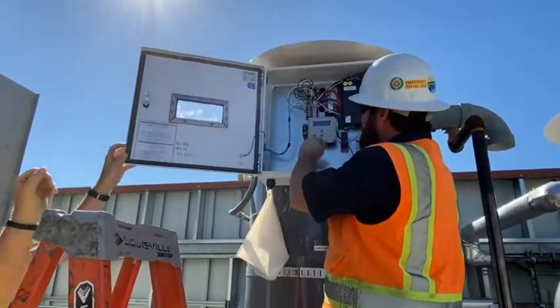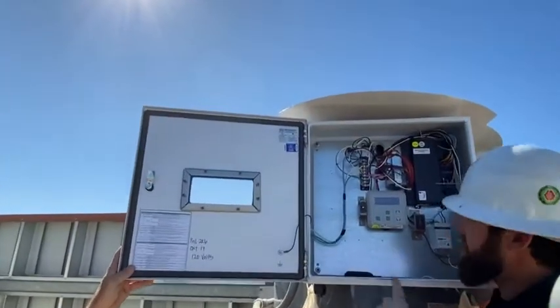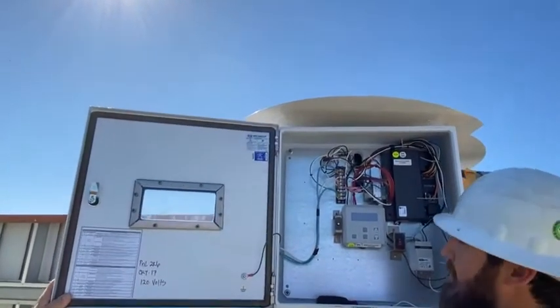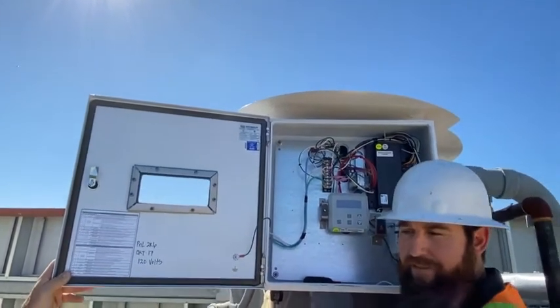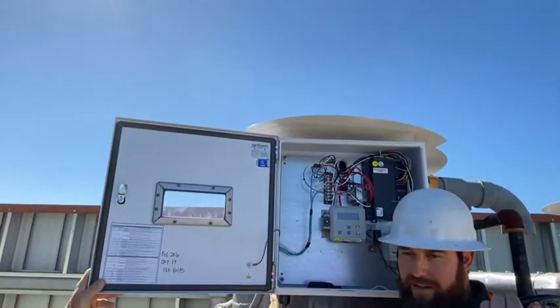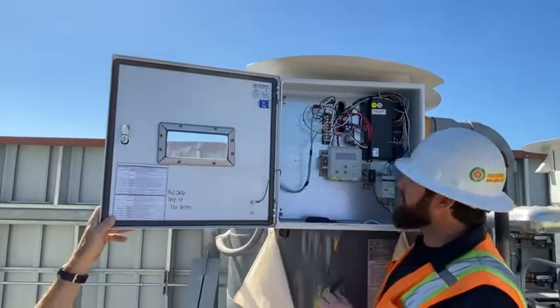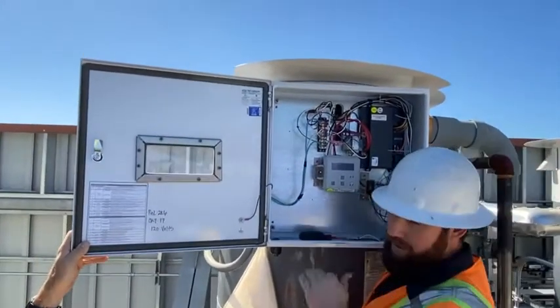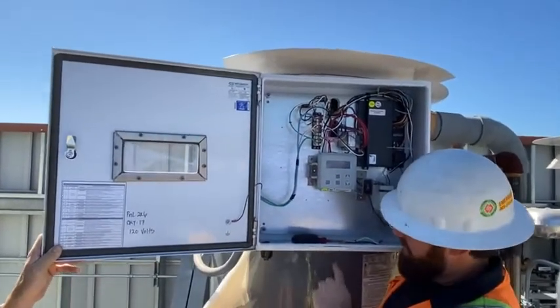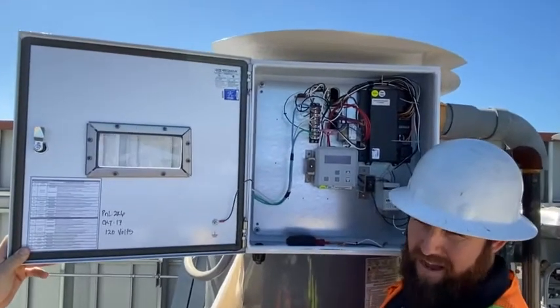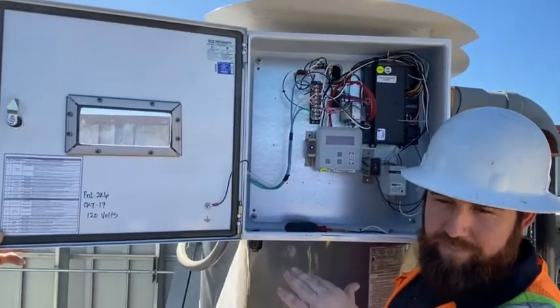It's kind of hard to read. Right now we're just in standby mode. We're at temp. The water heaters are set for 140, trying to maintain 140 degrees in the tank. It will fluctuate at the water heater side to about 5 to 8 degrees above 140.